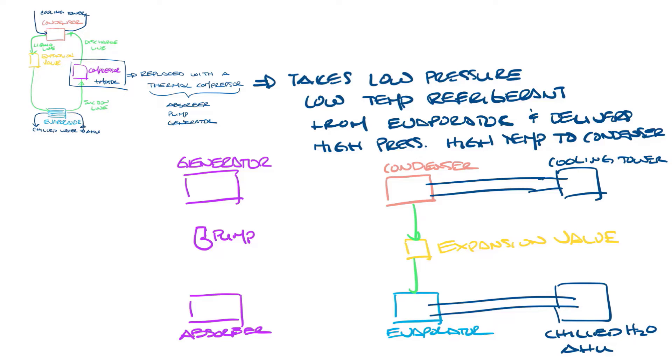Now let's go and look at this thermal compressor. Inside the absorber is lithium bromide and water. Because the lithium bromide is attracted to the water, they form a dilute solution. This solution is easily pumped through the pump to the generator.